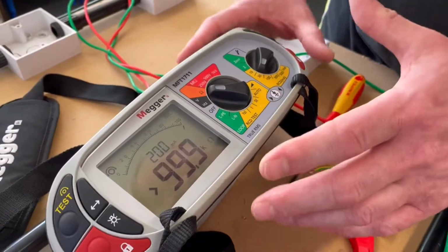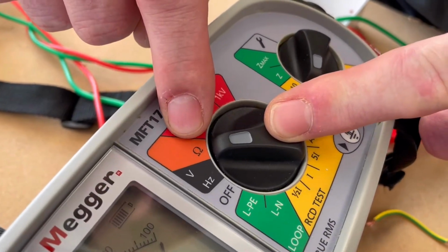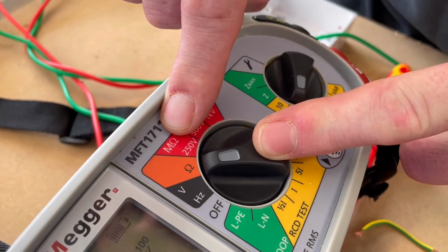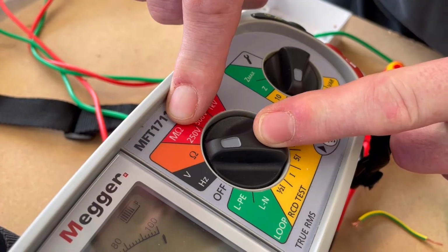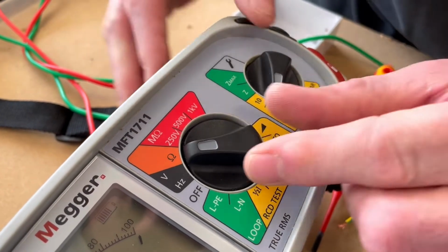So in order to carry out our insulation resistance test, we need to come back to our machine and change the scale. We're currently on the ohms scale. We're going to stay in ohms, but this time it's going to be in the megohms scale. Often on the channel, I still call it megger, and I always get picked up on it. That tends to be a bit of slang, doesn't it, for megohms. So I'm going to move it to the megohms scale.